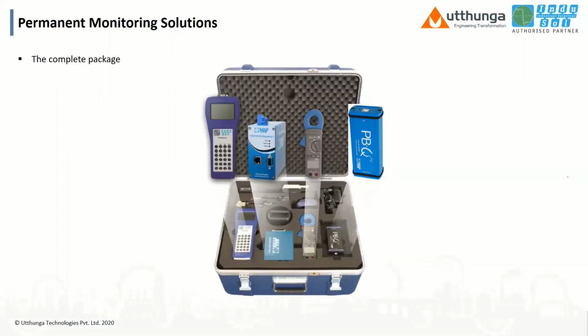So this is our complete package for maintaining Profibus networks. Not only maintaining, but also permanent monitoring. You have the supervisor. The PLC is always a supervisor, but you need an inspector. The Inspector always monitors the data traffic in the communication network, and it will give correct information and even time stamping and history of events that can reduce your profit loss in the network. PBQ1 is for the voltage analysis, the Profitest is for cable testing, and this is the EMC check. The EMC check is the shield current checking for the Profibus cable.